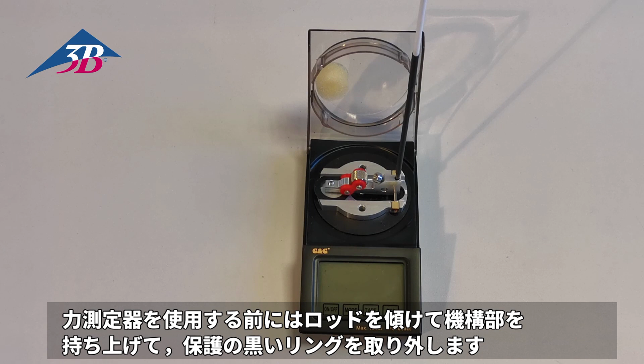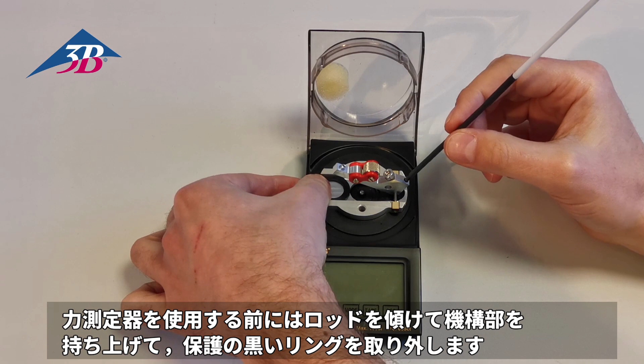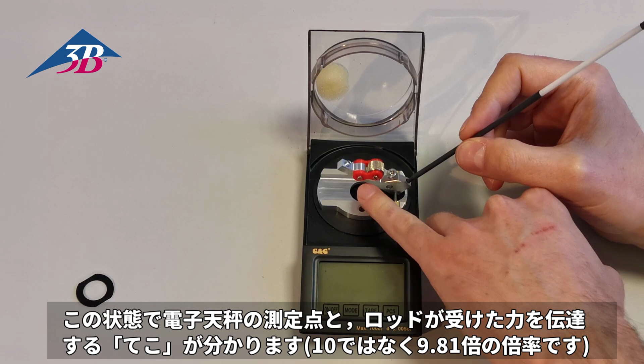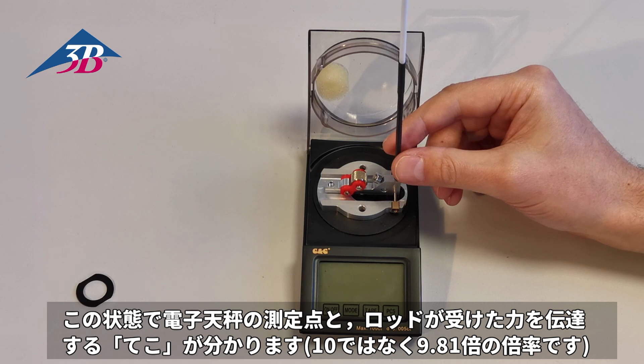Okay, let's go into details. Before using the force meter, make sure to remove this black ring here, which protects the balance. Here you can see where the force is measured, and here you see the leverage, which has a factor of roughly 10. So now you switch on the balance. If the balance doesn't show 0, press Tare to set it to 0 and make sure the mode is in gram. Due to the leverage, 1 gram is 1 millinewton and milligrams are micronewtons. So the balance is able to measure forces with micronewton.